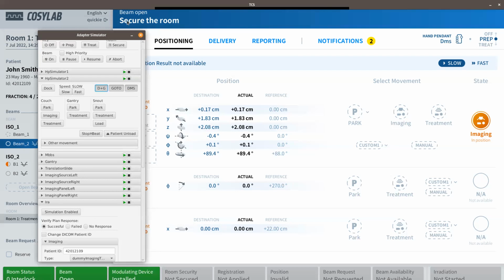And part of procedure is to make sure that this is the case. And it usually looks like that radiotherapists or some technicians go through the facility, through the accelerator area, to the treatment room, seek for hidden corners, and press some buttons on the walls to confirm that nobody is in the facility. And this process is usually guided by the safety system. And at the end, when this procedure is finished, so room is secured, the safety system informs the TCS that room is secured. But for this purpose, I will just simulate the safety system. So we'll just press the button, and now everything is secured and we are ready to acquire CT image.